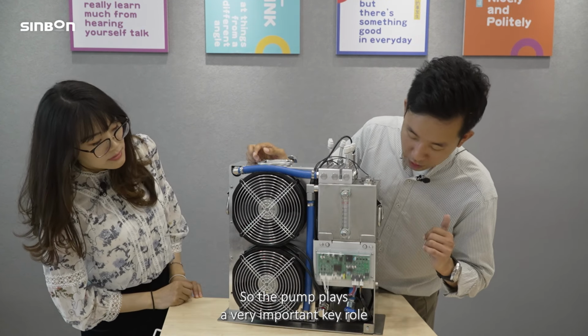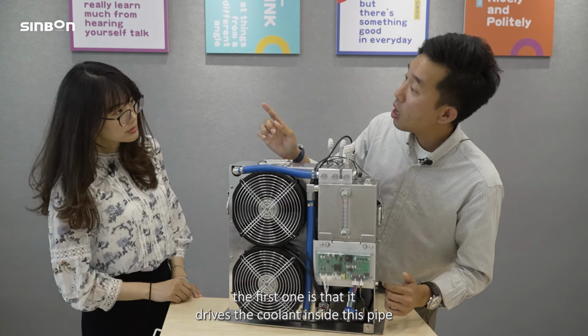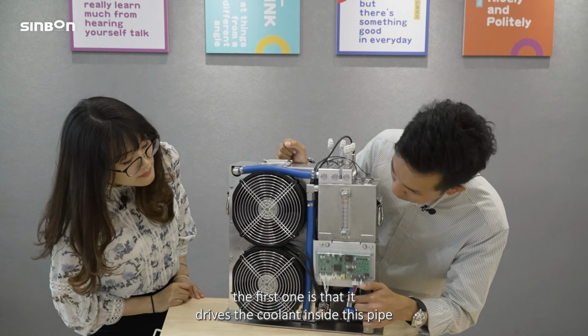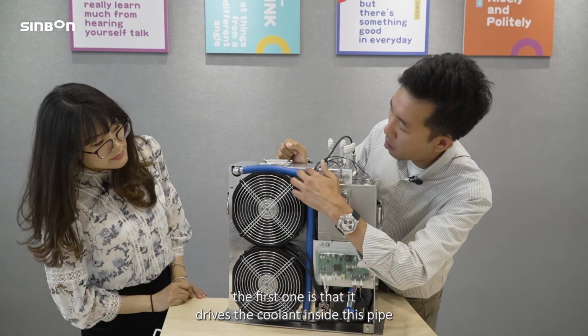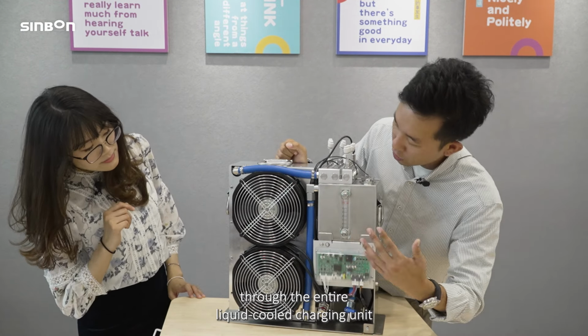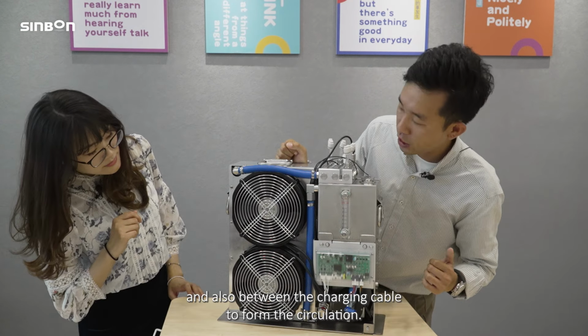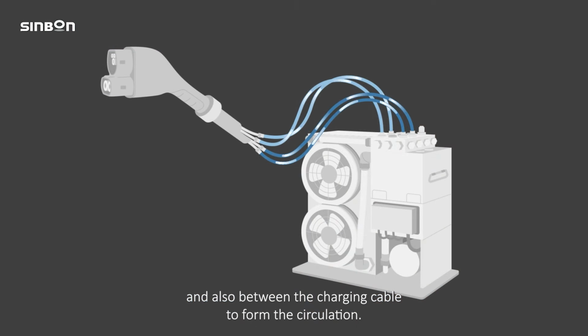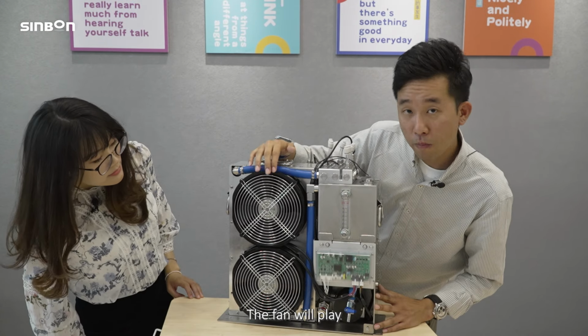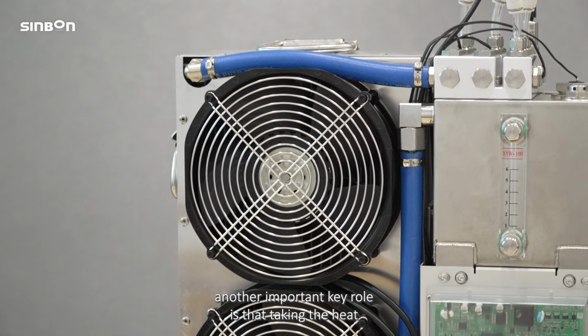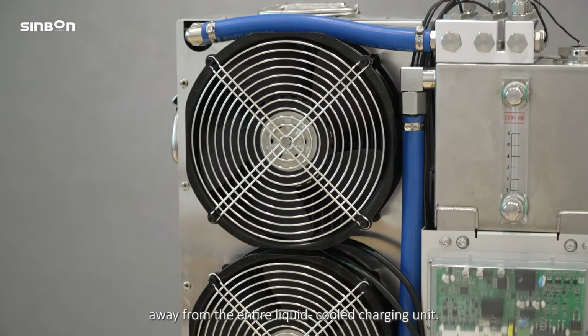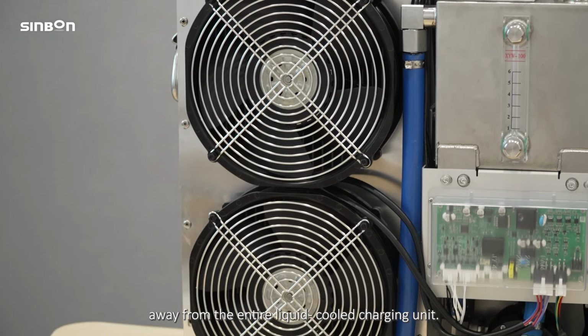So the pump plays a very important key role. The first is that it drives the coolant inside this pipe through the entire liquid cooled charging unit and also between the charging cable to form the circulation. So once the charging cable coolant comes back to the charging unit, the fan plays another important key role, which is taking the heat away from the entire liquid cooled charging unit.